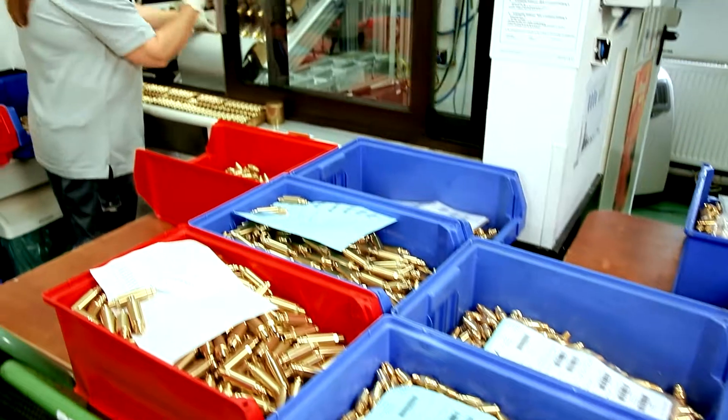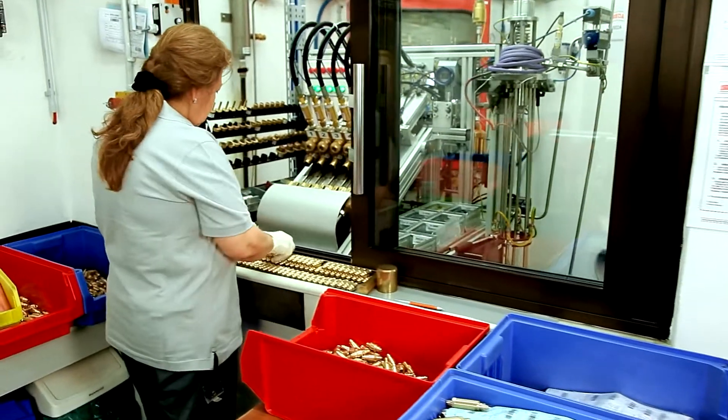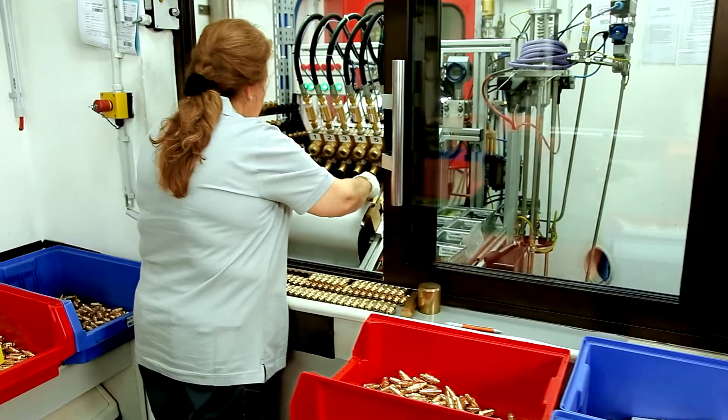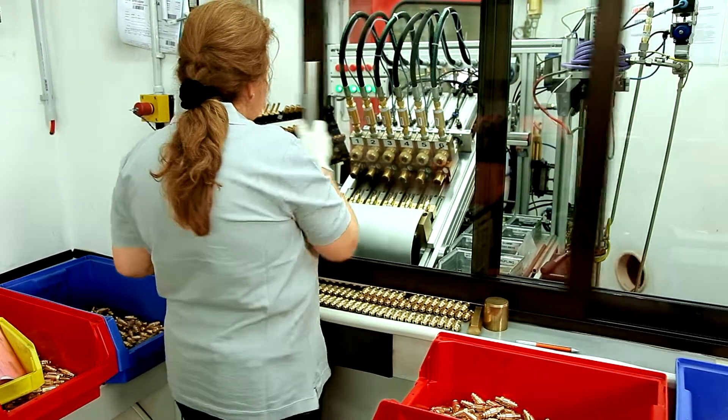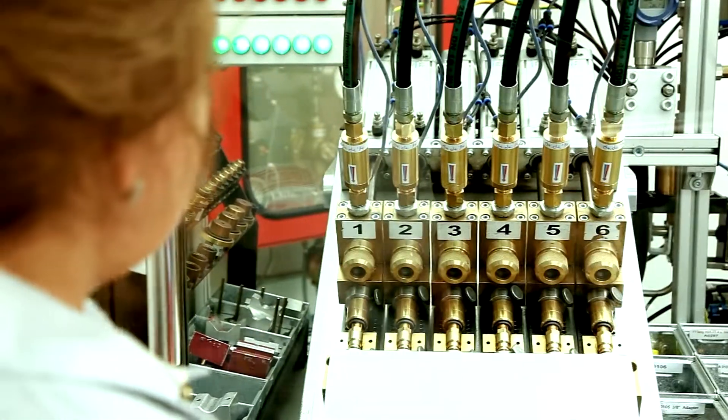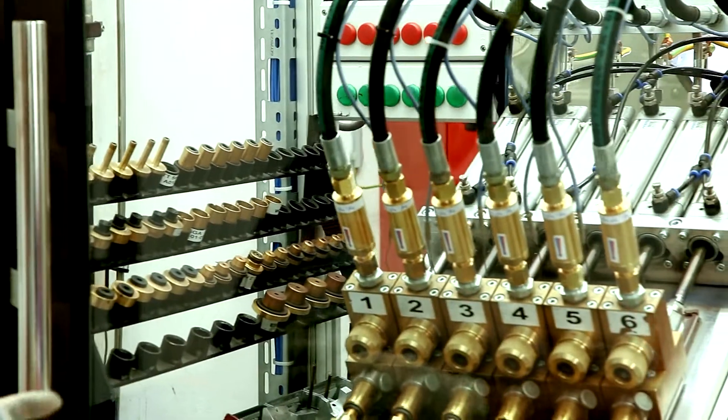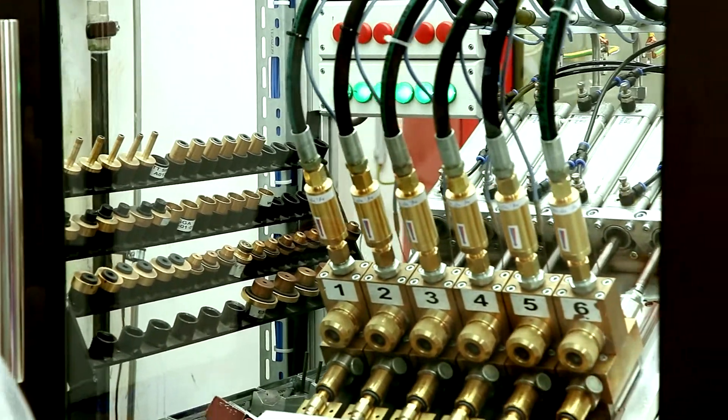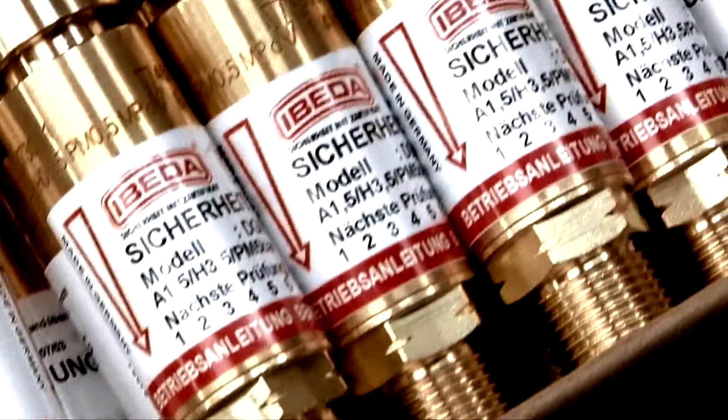The most important manufacturing step is the 100% function test of all safety devices. Each fitting is subjected to a flashback with a fuel-oxygen mixture at maximum operational pressure to determine faultless functioning of the flame arrestor.